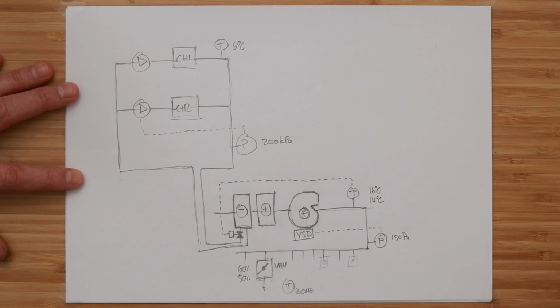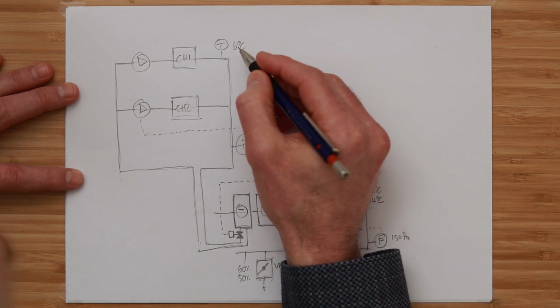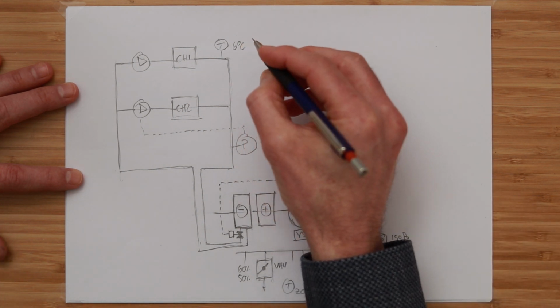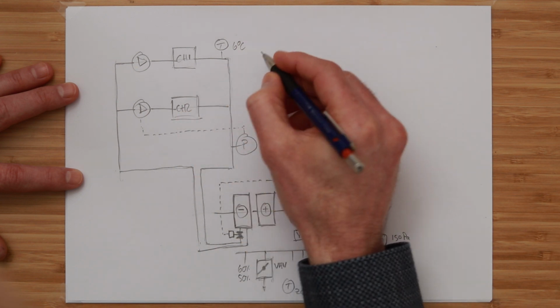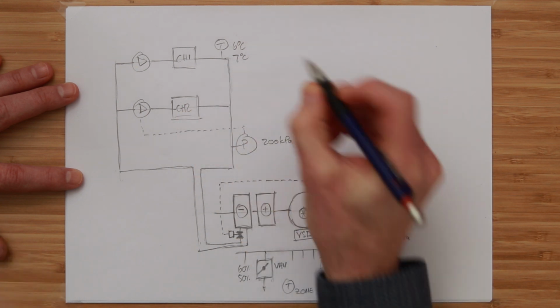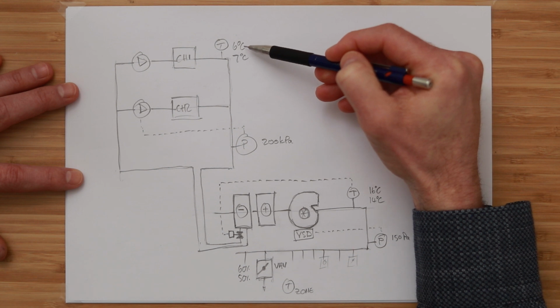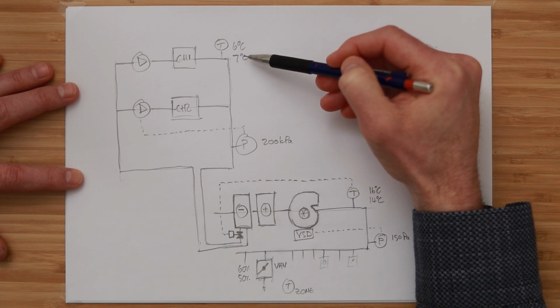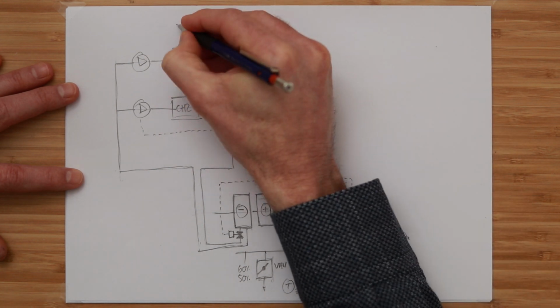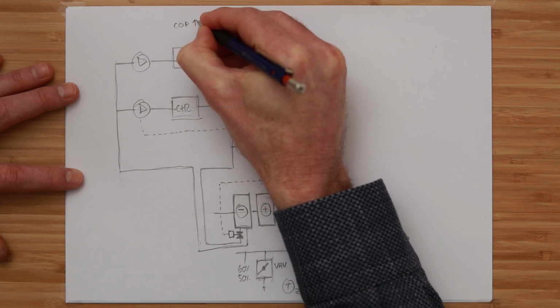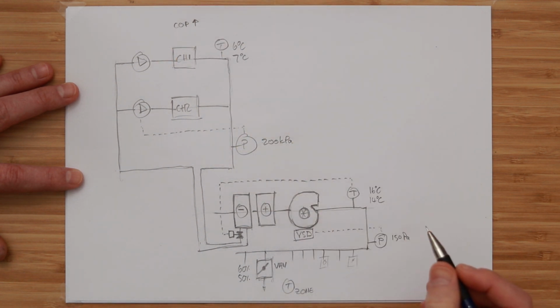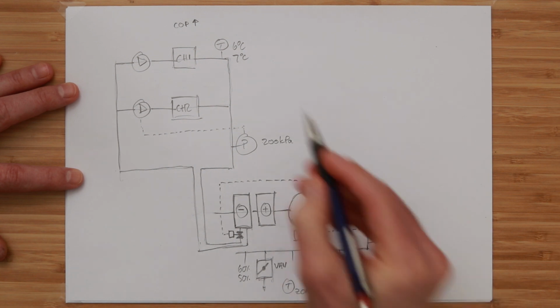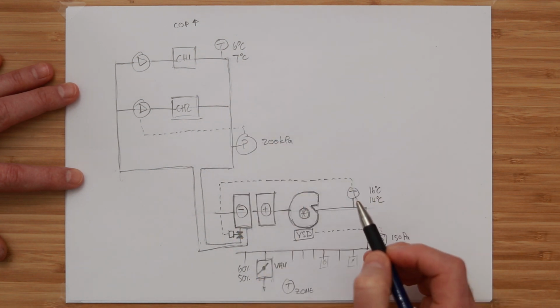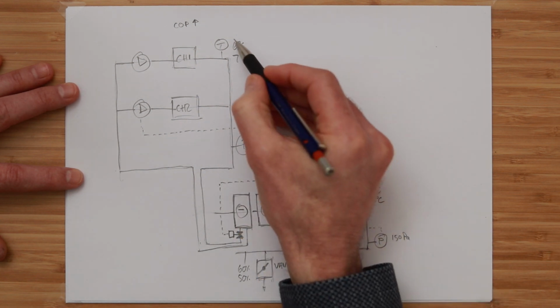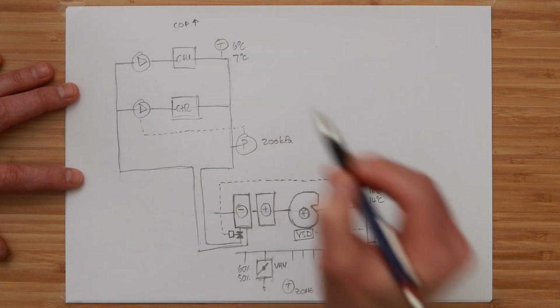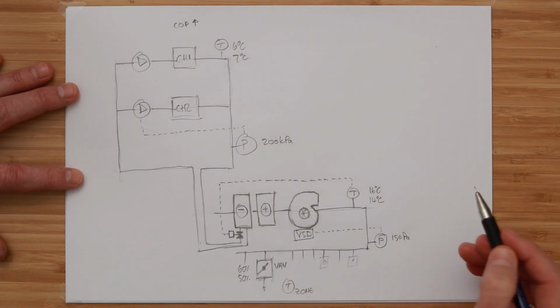The other thing that we do is we have an optimization strategy where we increase the chiller's temperature slightly. So when we increase the chiller's supply water temperature slightly, what happens is the chiller's COP increases. The coefficient of performance of the chiller increases as we slightly increase this temperature.